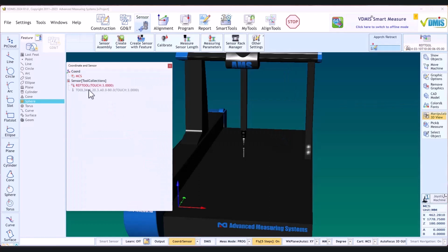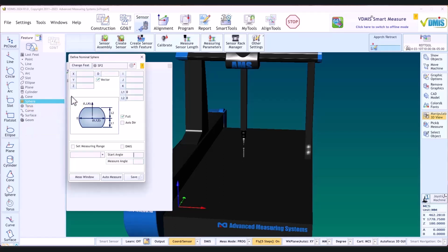Next step is to define the calibration sphere. To do that, we click right mouse button on the title, Sphere, in the Features database, then we click on the entry, Create New Nominal Sphere. For sphere coordinates we can type any value or even just 0, because those coordinates will be updated once we locate the sphere. For sphere diameter we need to type the exact diameter, then we type the sphere shaft vector.